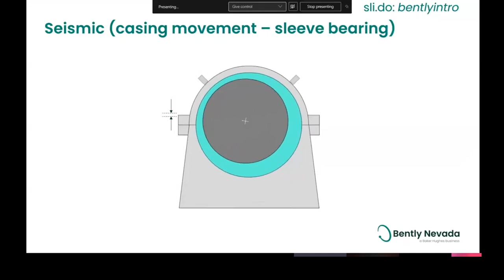And finally, we have accelerometers. The construction of these is such that they've got a little piezoelectric crystal mounted and fixed to the frame of the accelerometer. And on the other side of that piezo crystal is a mass. So again, since this is mounted on the machine, as that case moves up and down, this mass on this other side here wants to stay in place. So as that mass moves relative to the casing, it puts a stress on that crystal, which produces a little electric charge, which we can then measure, and that outputs a native acceleration unit. Again, that would be meters per second squared, inch per second squared, or standard gravity, or G's.